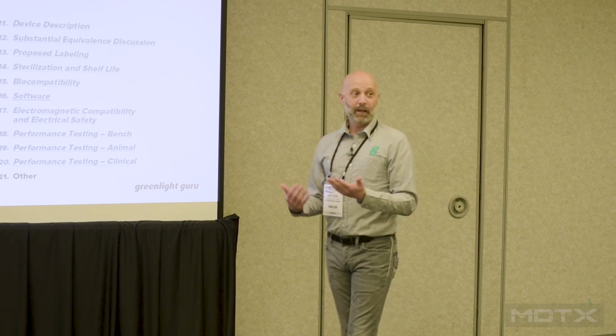Now, I assure you that today they do not allow that. Don't submit your 510K with an I promise statement. Do not do it. I mean, we talked about risk-based QMS in the earlier session. This is one of those risks. You can take the risk, and I bet that it gets rejected. So I don't know if you have any thoughts or experience on that.